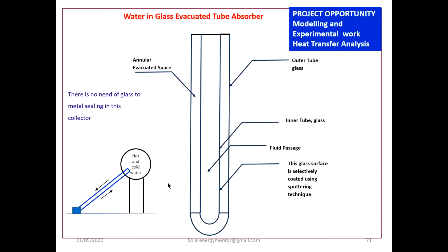However, they have certain disadvantages. These glass tubes are very delicate in structure. Even a heavy leaf of a tree, due to heavy wind, if it falls on this structure, the tube breaks. And if a crack appears in a single tube, then the entire system, suppose 100 tubes you arrange in a row, has to be brought down, and then you have to check for the fault. So delicacy of the tubes is a drawback.